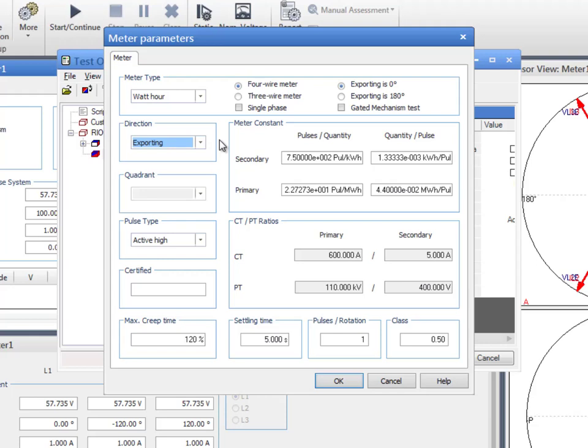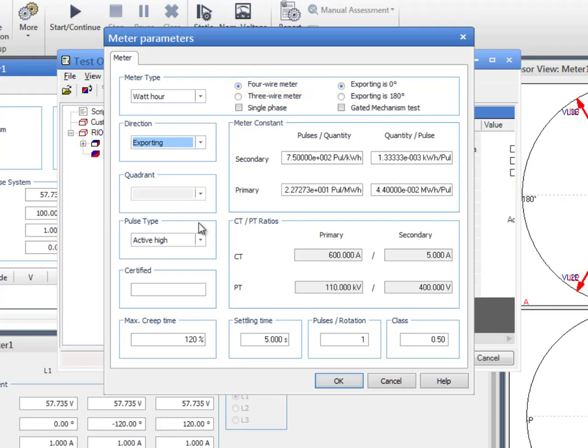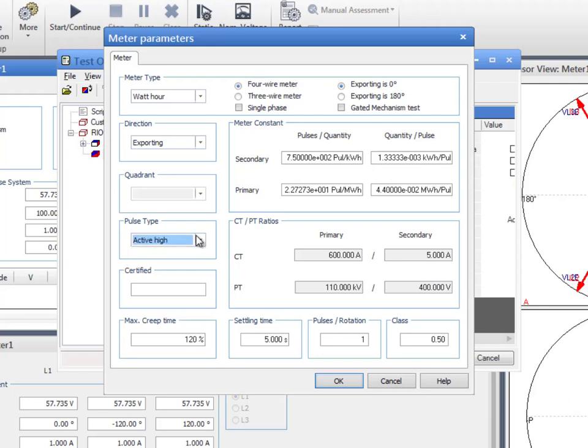The test can be performed with any balanced or unbalanced load for single-phase, three-wire, and four-wire meters. Since the meter under test presents inputs for three phases plus neutral, we select the four-wire option. The pulse type option can be set to active high or active low, which must match the meter under test in order to measure the pulse count accurately.